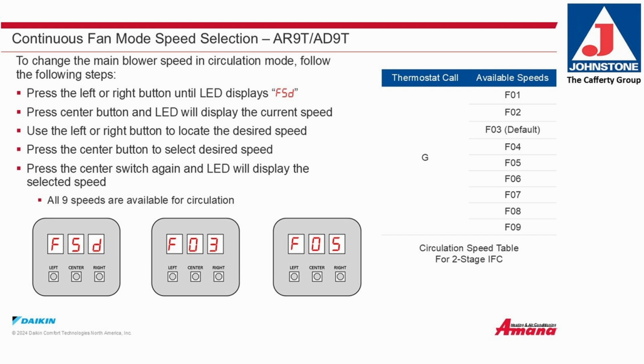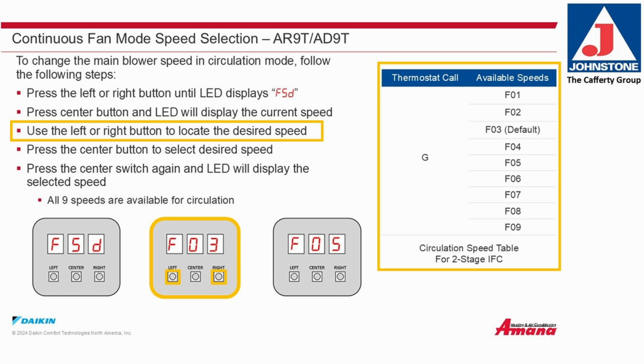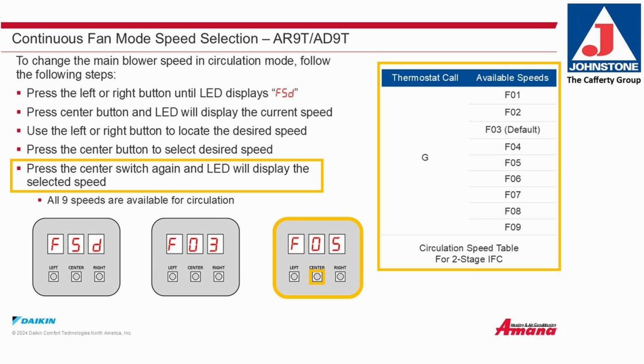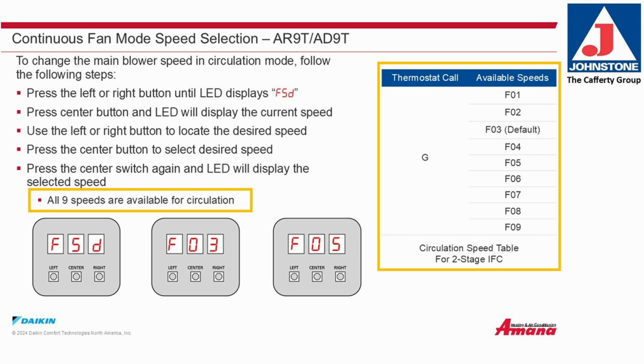Continuous fan mode speed selection. To change the main blower speed in circulation mode, follow these steps. Press the left or right button until the LED displays FSD. Press the center button and the display will show the current speed. Use the left or right button to locate the desired speed. Press the center button to select that desired speed. Press the center button again, the LED will display the selected speed. All 9 speeds are available for circulation mode.